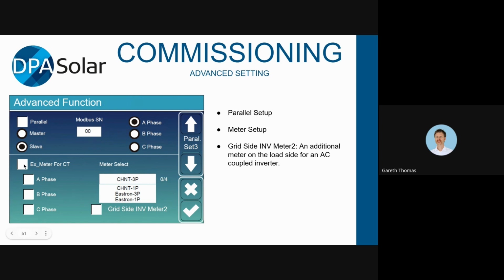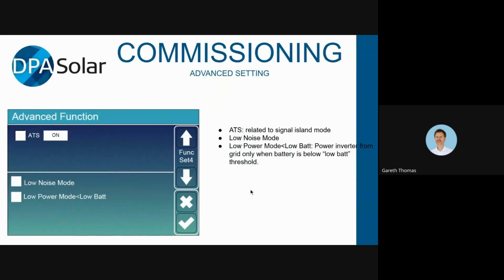If you're using an external meter, you're going to tick this box, external meter for CT, and then you're going to select the meters on the right-hand side here. The last page, advanced function, ATS. If you want to use that signal island port that we discussed before, you have to turn it on here. Low noise mode, I'm not 100% sure what that is. Do you know what that is, David? No, maybe it just regulates the fan. Maybe it just minimizes fan operation. Oh, yeah.